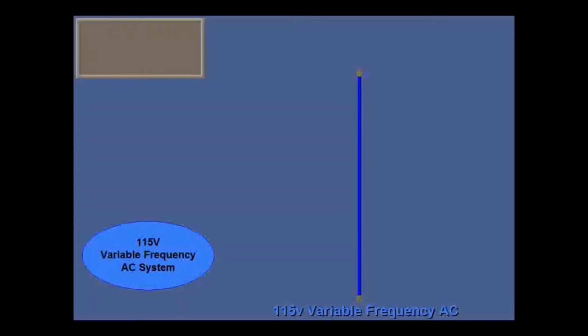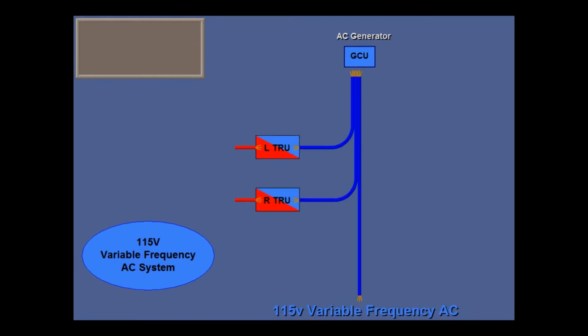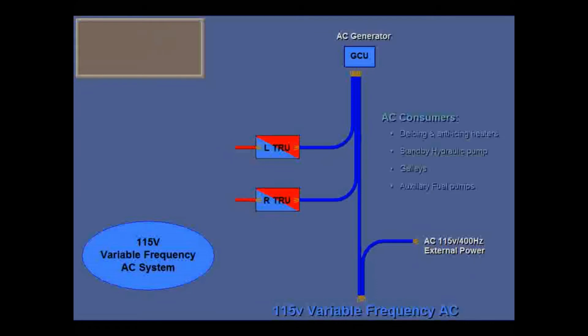There is also one AC system linked to the DC. The AC power sources are an AC generator mounted on the prop gearbox of each engine, which provides 115-volt 3-phase variable frequency AC through an AC generator control unit to the 2 TRUs, which in turn supply the 28-volt DC system. AC external 115-volt 400 Hz power can also be connected. The AC system powers these consumers.